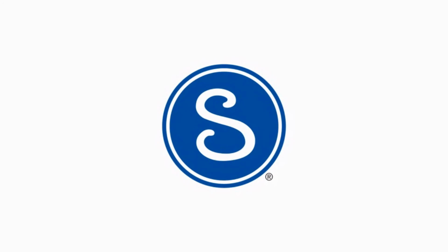I got one last question that's come in. And the question is, does the type of gas that you're using matter? Does that have an effect? Are there certain gases that should not be hooked up to an automatic changeover, or can any type of gas media be hooked up to that? Ooh, lots of great questions. So an automatic changeover should work for just about any type of gas.